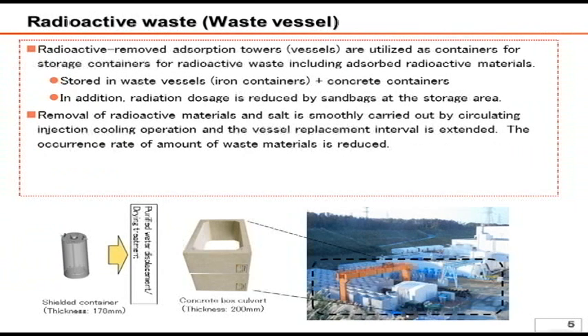This adsorption vessel contains zeolite inside which adsorbs cesium, so that the apparatus itself is radioactive waste. Accordingly, the apparatus has to be properly stored while its surface radiation level is under close surveillance. We plan to store the apparatus — which itself is a shielded iron container with a 170mm thickness — in a square-shaped concrete box called a box culvert. The construction of such storage places is currently in progress and apparatus has been stored there as construction is completed. Regarding the inside of the apparatus, water is removed prior to storage as water may produce hydrogen and oxygen due to radiation decomposition.